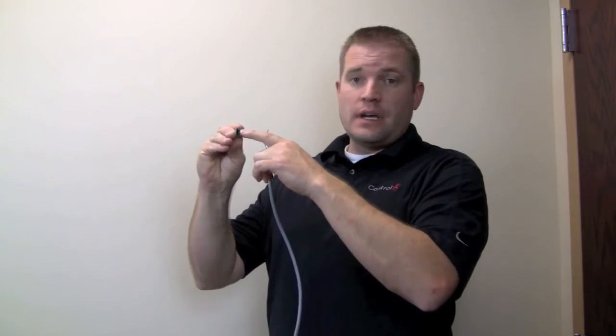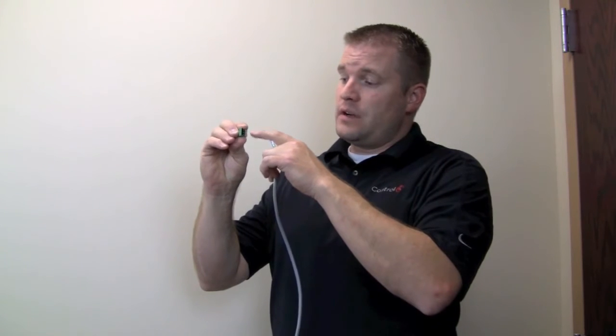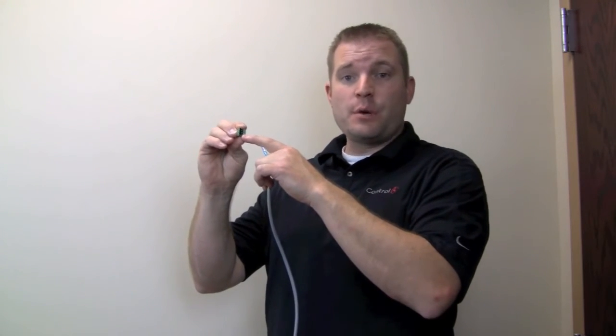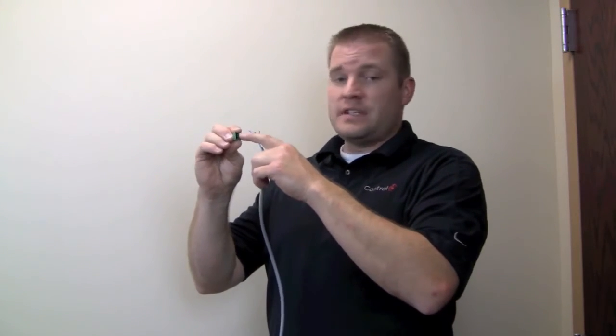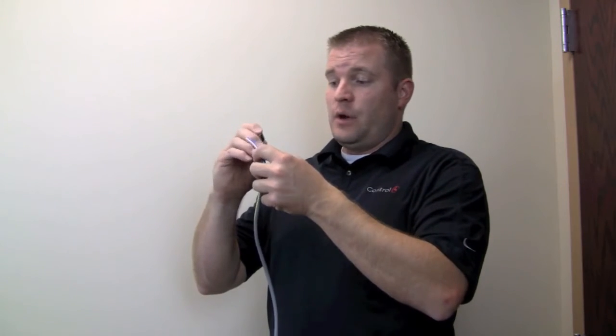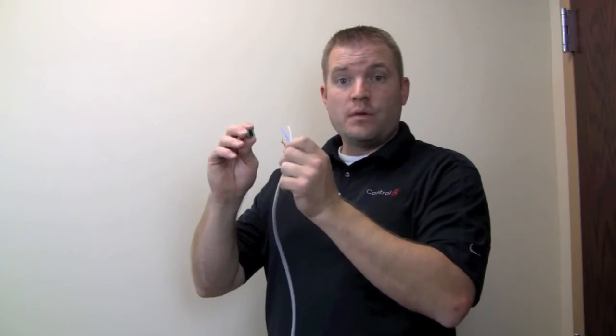On the back, there's four different terminals here: a ground, a voltage plus, that's going to be your positive and negative, and then there's data minus and data plus. And whatever color wires that you used back at the gateway, you want to obviously match here on the keypad.